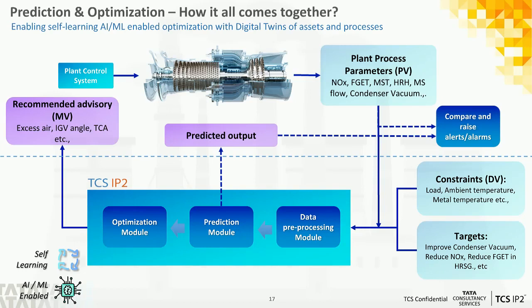So first thing we do is we select the manipulated variables, such as the IGV angle. Next, we identify disturbance variables and constraints, so for example load, metal temperature, etc. And then lastly, we select the plant process variables such as NOx. So the type of data we use to build the digital twin is both steady state as well as plant test data. Next, we use multiple algorithms, perform sensitivity checks, and then tune the model to validate it. And these models are self-learning.